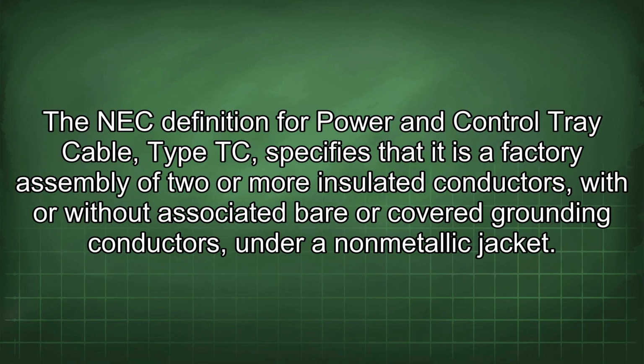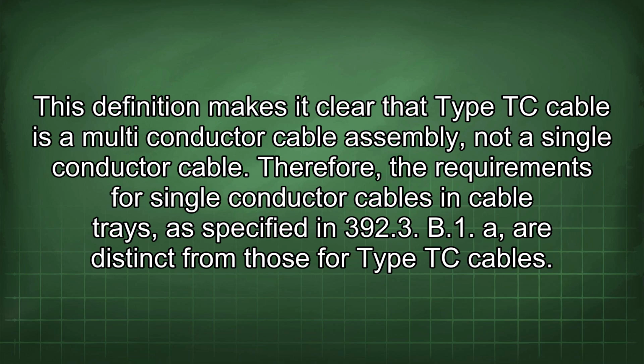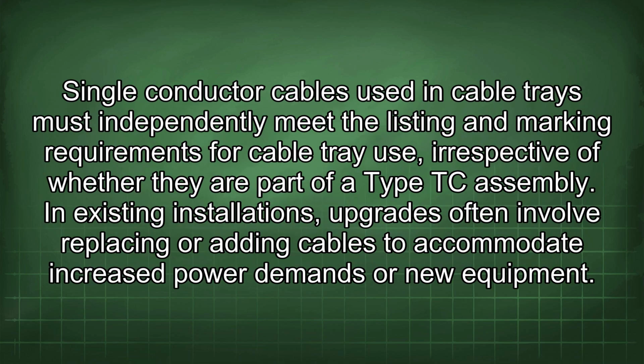The NEC definition for power and control tray cable Type TC specifies that it is a factory assembly of two or more insulated conductors, with or without associated bare or covered grounding conductors, under a non-metallic jacket. This definition makes it clear that Type TC cable is a multi-conductor cable assembly, not a single conductor cable. Therefore, the requirements for single conductor cables in cable trays, as specified in 392.3(B)(1)(a), are distinct from those for Type TC cables. Single conductor cables used in cable trays must independently meet the listing and marking requirements for cable tray use, irrespective of whether they are part of a Type TC assembly.